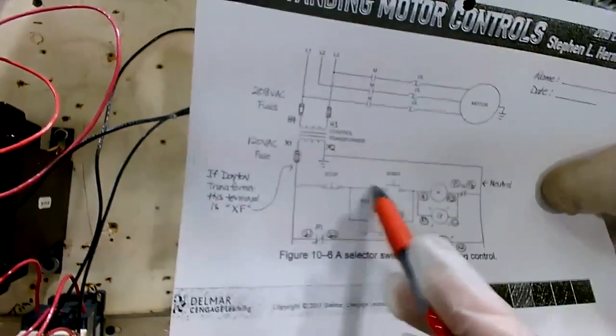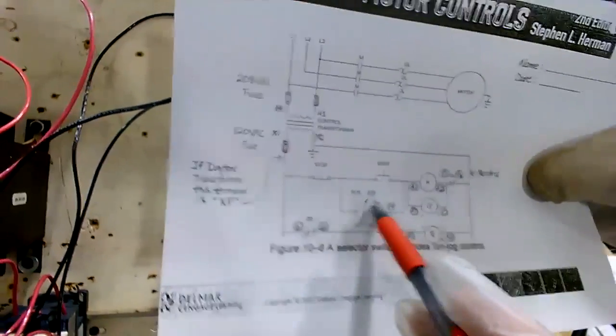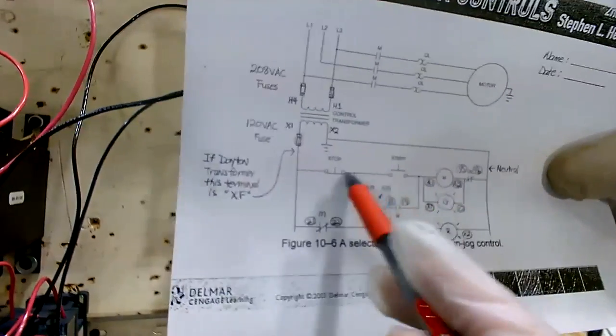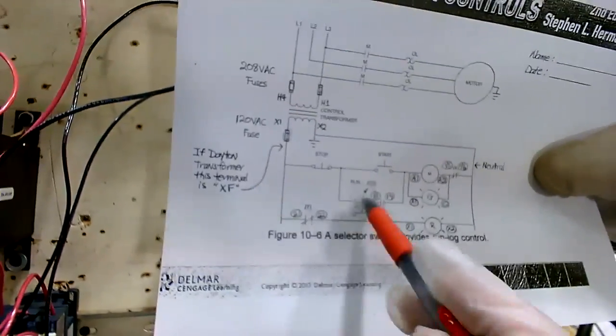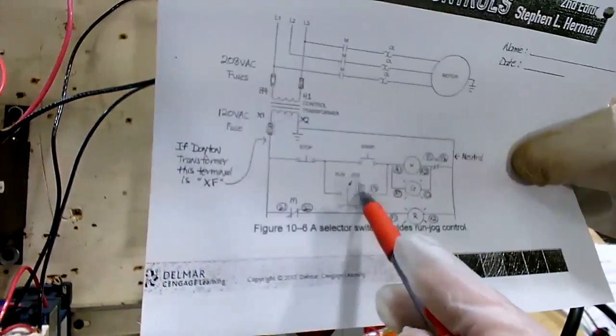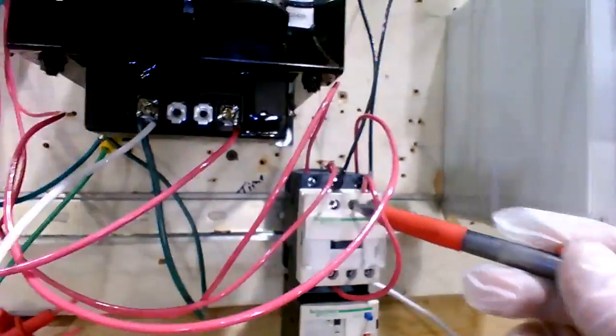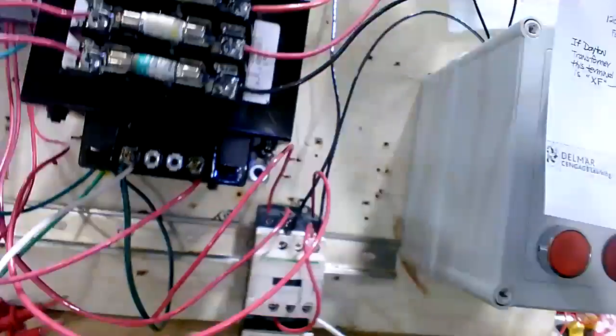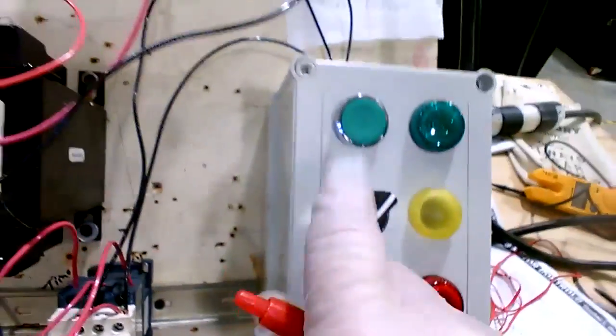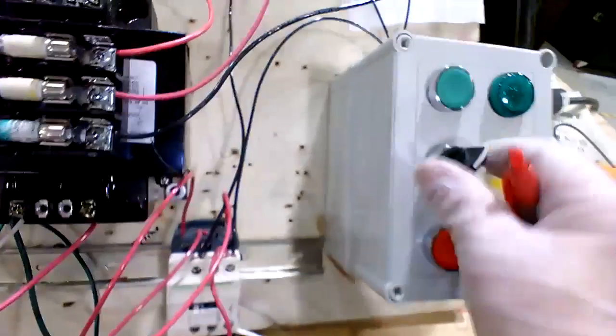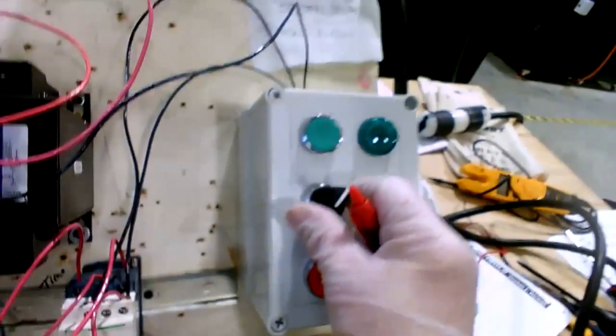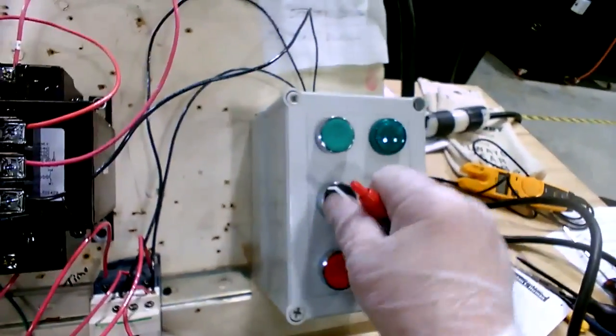You go in there to where originally you had a wire going from between stop and start going straight to 13. Originally, what you have right now is straight from here to here without that in there. You go in there, you remove 13, lift 13 off of here. And then you're going to run that same wire, pull it off of 13, and come out here, go to that switch. Leave that switch and go back to 13. Then this switch can actually connect 13 like original or get rid of it.